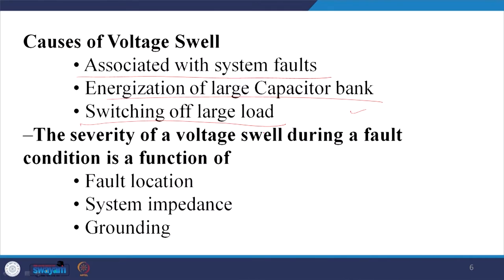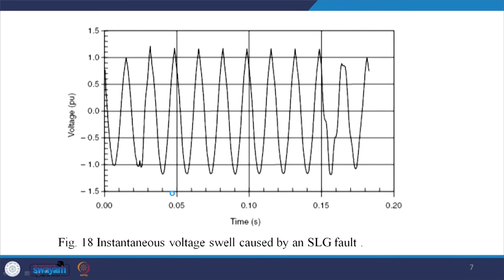Switching off a large load can also cause a swell because voltage builds up. We need to identify the severity of voltage swell during a fault condition as a function of fault location, where the open circuit occurs, fault system impedance, and ground impedance. For example, an instantaneous voltage swell is caused by a single line to ground fault in the other two lines — there is distortion, the voltage swells, and then it sags again. This phenomenon occurs to other healthy lines in case of a single line to ground fault.